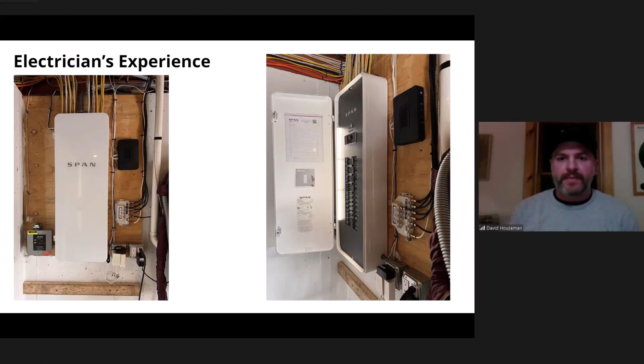Duration too, basically, it all depends on if you need an upgrade or on the quality of the meter socket outside and your drop. If you already have 200 amps, the load side of the meter socket wire may need to get changed out, but you can basically leave all that there if it's in good condition and just change the panel out, which is what I did here in Colchester.